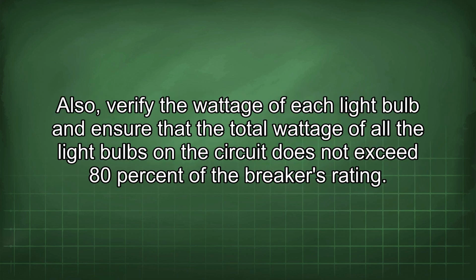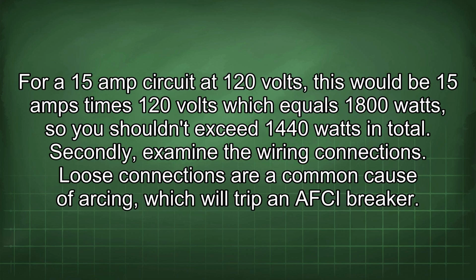Also, verify the wattage of each light bulb and ensure that the total wattage of all the light bulbs on the circuit does not exceed 80% of the breaker's rating. For a 15 amp circuit at 120 volts, this would be 15 amps times 120 volts, which equals 1800 watts, so you shouldn't exceed 1440 watts in total. Secondly, examine the wiring connections. Loose connections are a common cause of arcing, which will trip an AFCI breaker.